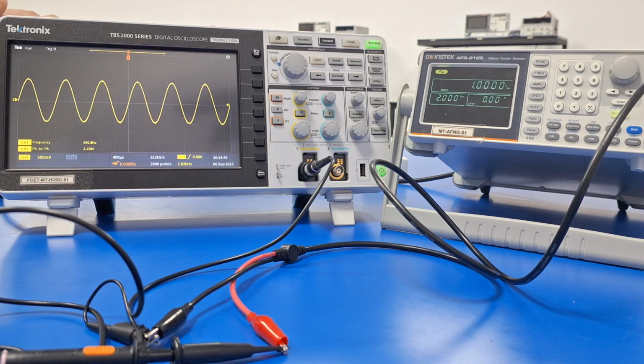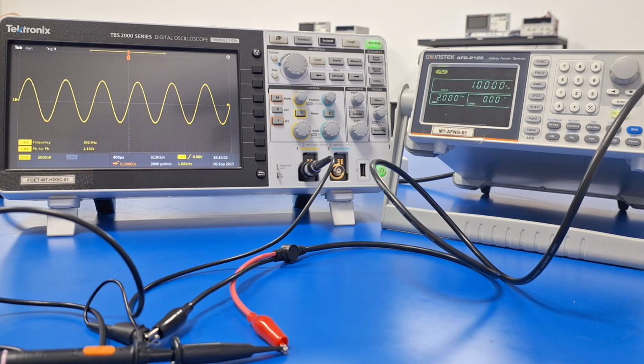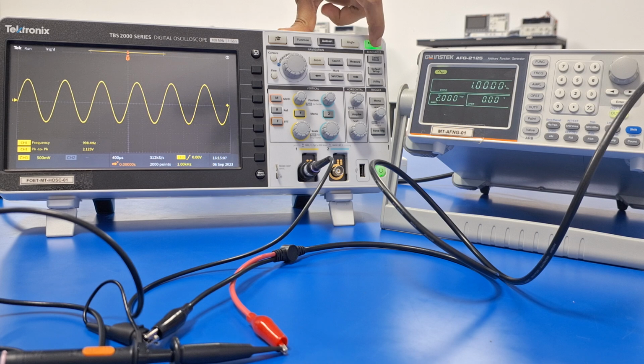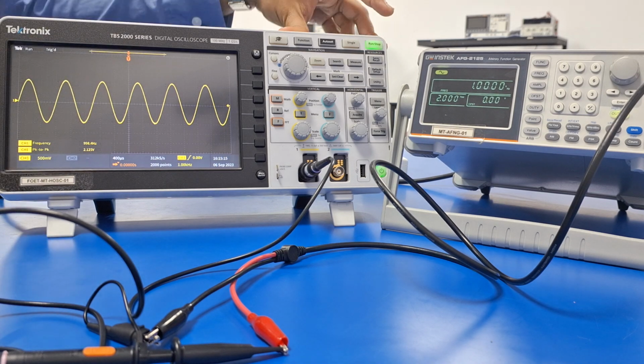And lastly, before taking any concrete measurements on your oscilloscope, you need to freeze this signal. There are 2 ways to freeze the signal because this is fluctuating, so you need to have one set of concrete measurements. You can either press the run stop button. This run stop button is there in almost all the oscilloscopes. This will essentially stop the signal, and again if you press it, it will resume the signal.